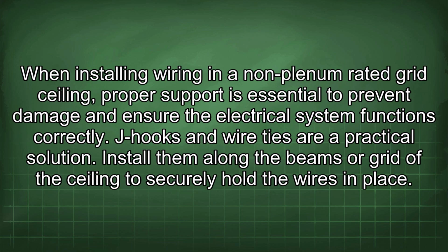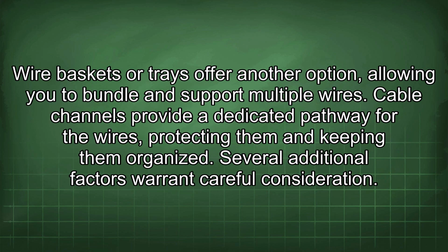When installing wiring in a non-plenum rated grid ceiling, proper support is essential to prevent damage and ensure the electrical system functions correctly. J-hooks and wire ties are a practical solution. Install them along the beams or grid of the ceiling to securely hold the wires in place. Wire baskets or trays offer another option, allowing you to bundle and support multiple wires. Cable channels provide a dedicated pathway for the wires, protecting them and keeping them organized.